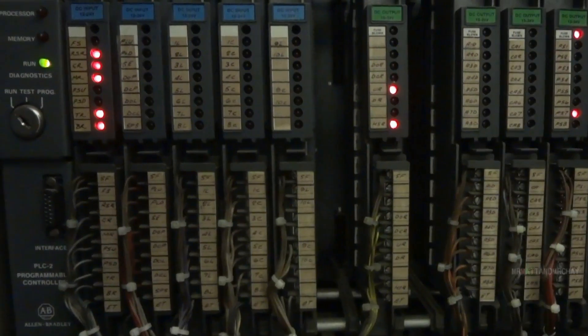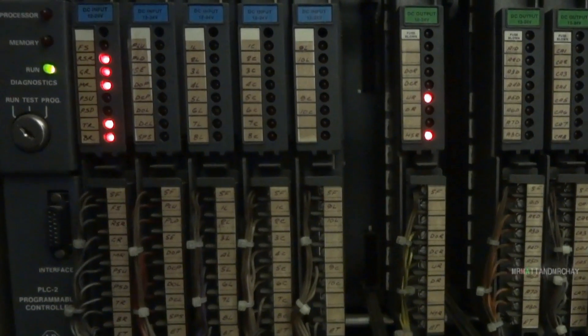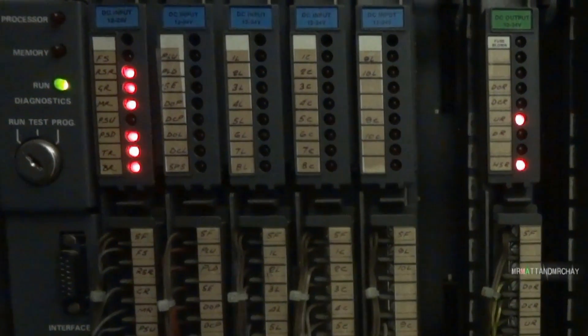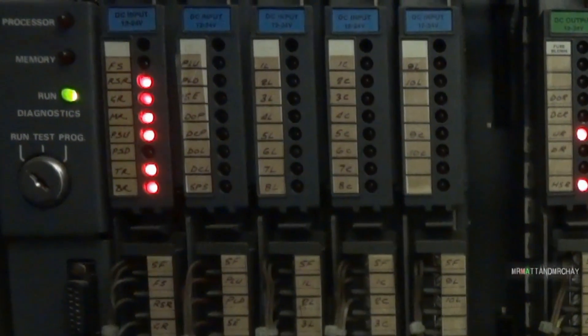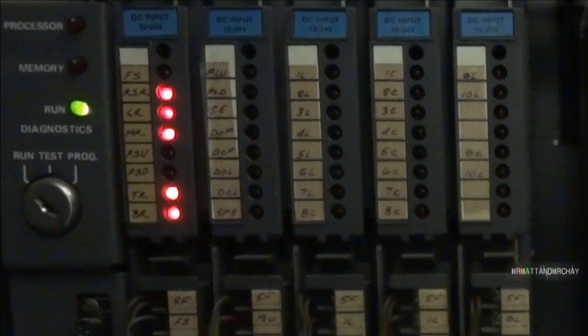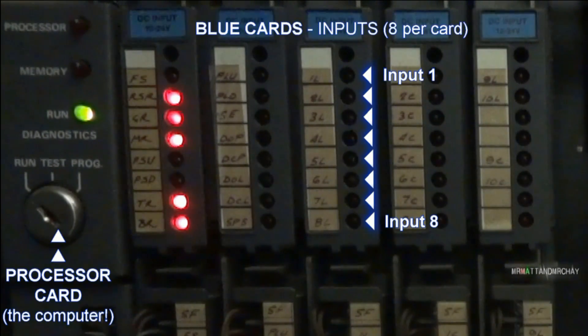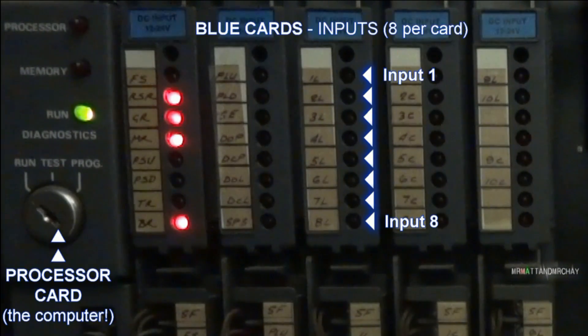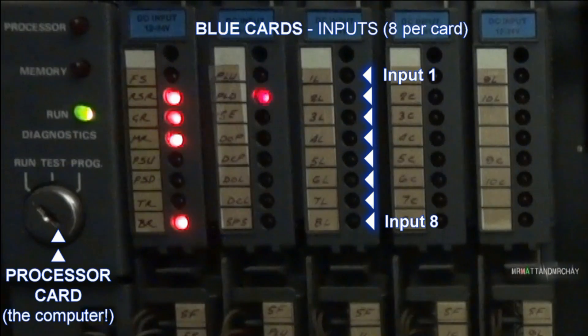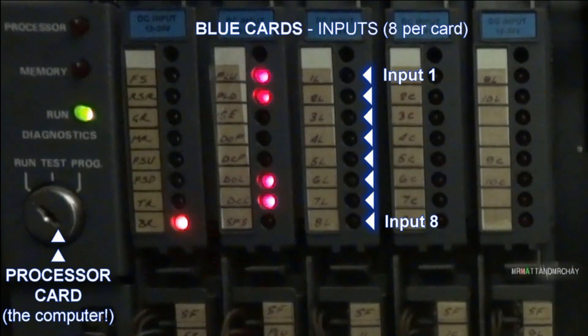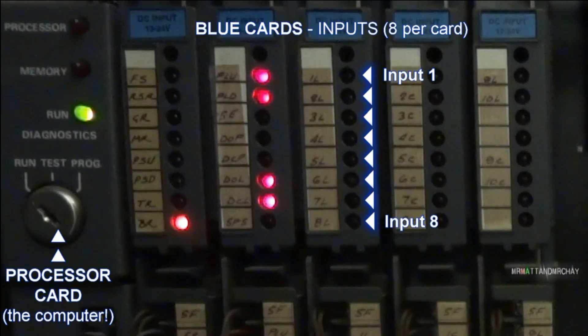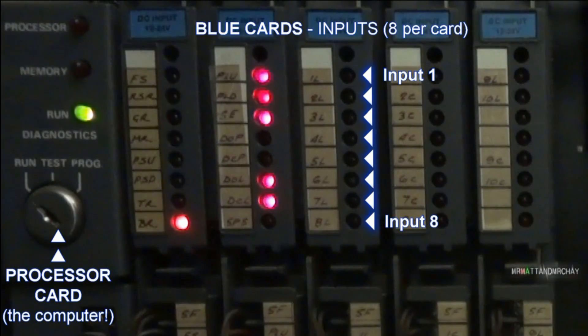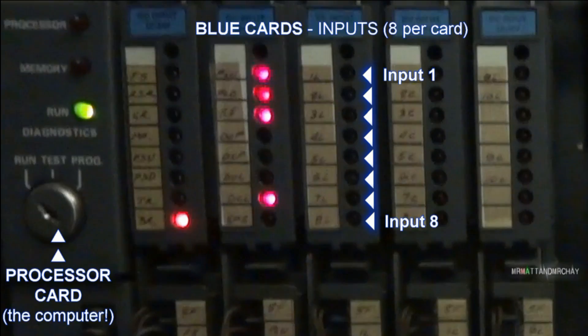These blue cards are for inputs, eight inputs on each card. Connected here are switches or devices that give the controller information on or off. Mostly these inputs are call buttons, limit switches and feedback from relays elsewhere on the controller.